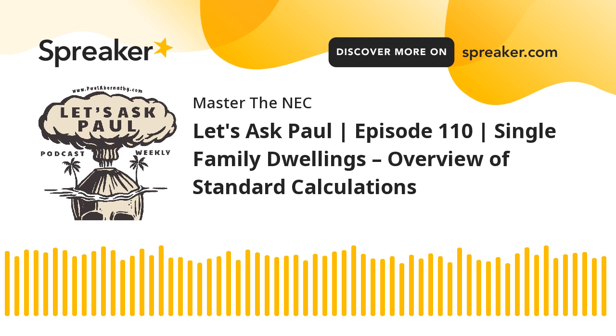All right. So once we got all that, all we're doing now is adding up all those steps. We take the calculation that we did for our general lighting, general use receptacles, small appliance and laundry, where we applied 220.42. We take the value from all our fastened-in-place appliances that are rated a quarter horsepower or 500 watts or greater. If we applied the 75%, that's great. If we didn't, then we take it at full value. We did the clothes dryers. We did the cooking. We had the heat versus AC in our case for the single family dwelling. And then we found the largest motor and we did it at 25%. We add all that up.